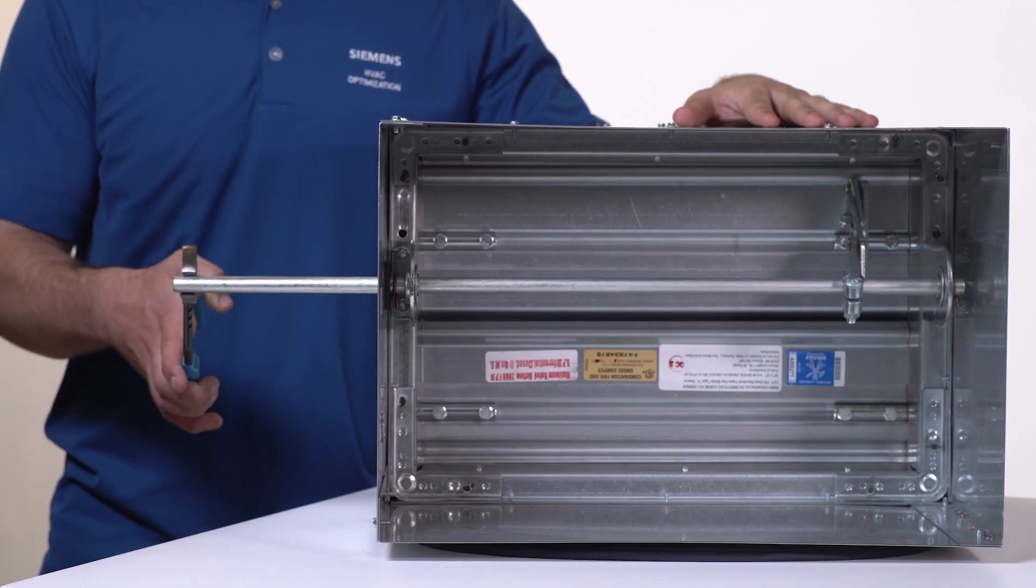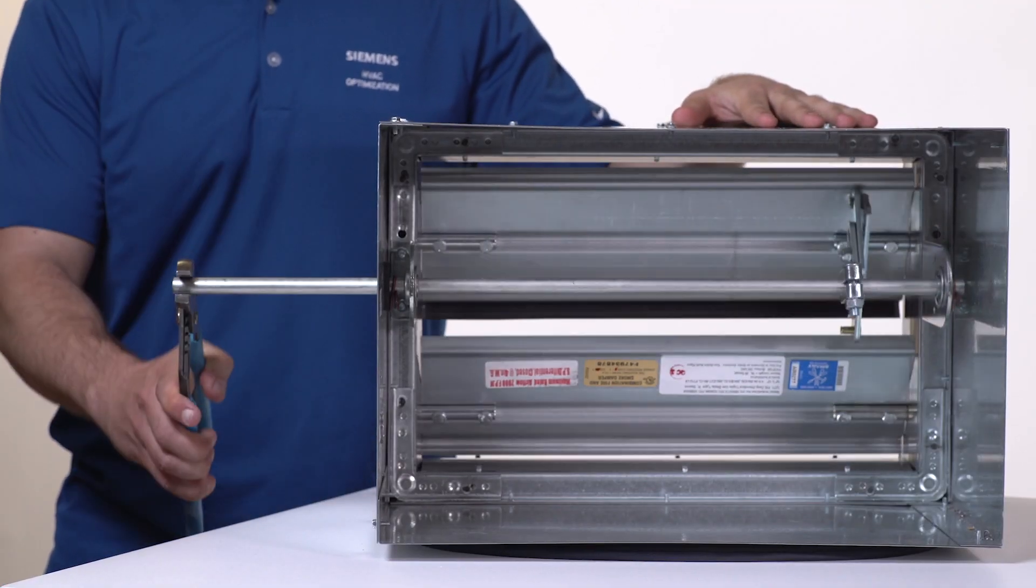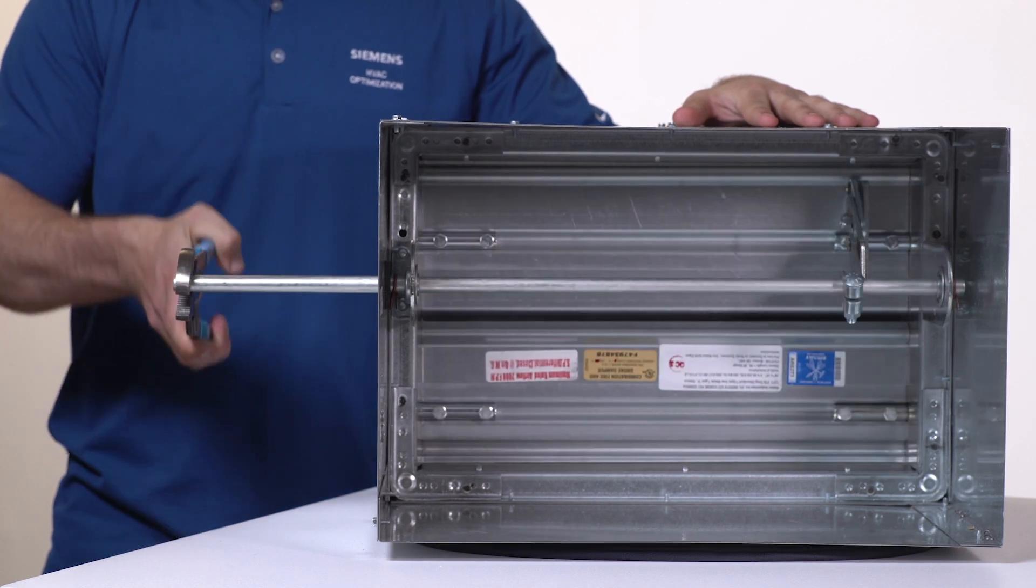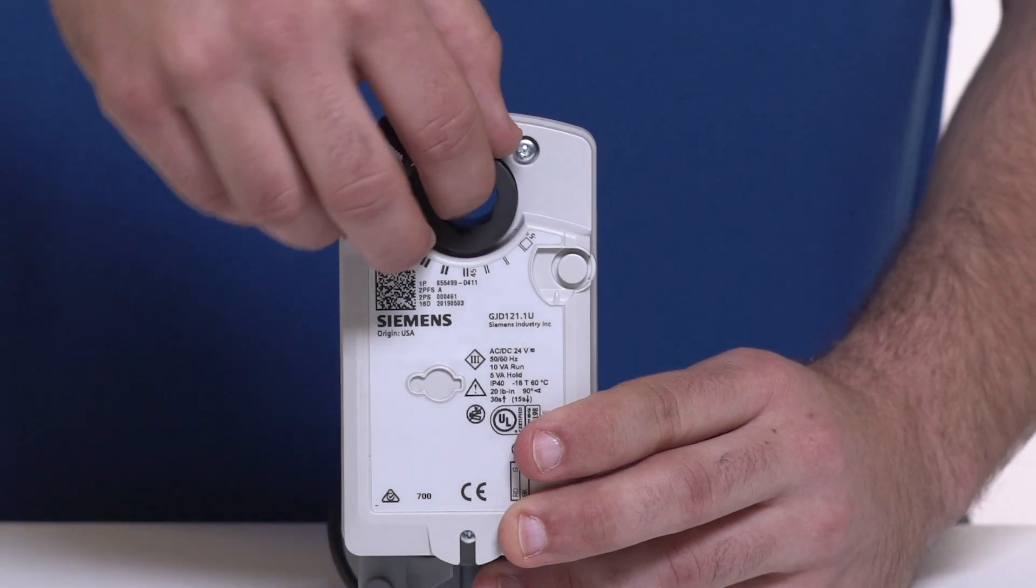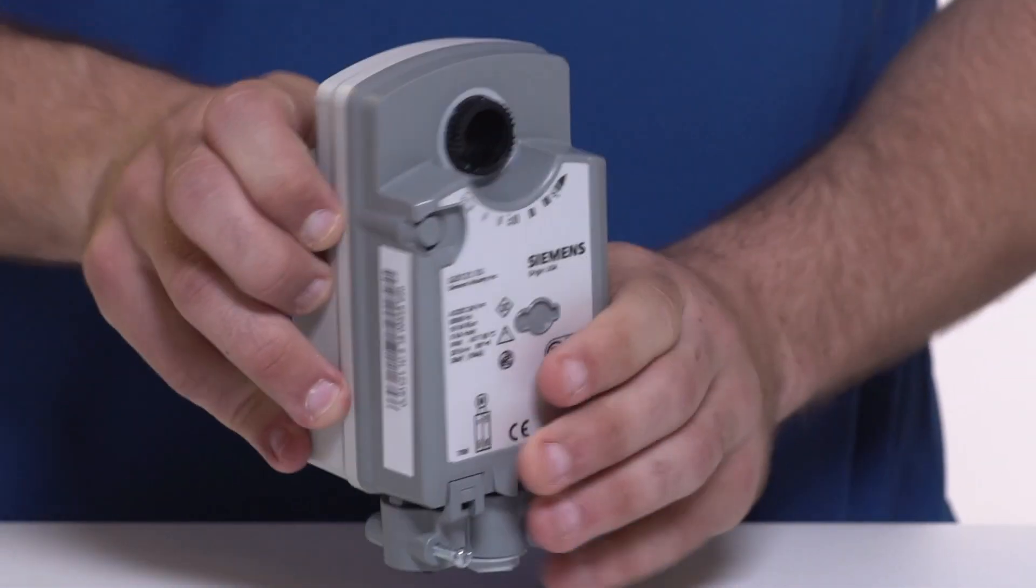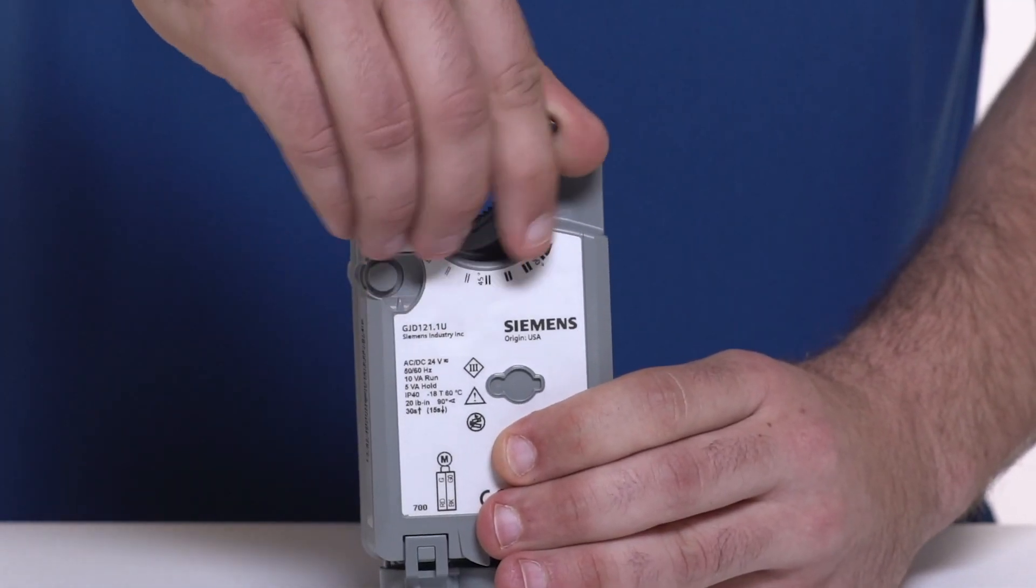Now determine the orientation of the actuator based on the rotation of spring return to fail open or fail close. If the actuator is not in the desired rotation, remove the locking clip and shaft adapter and reassemble on the other side of the actuator.